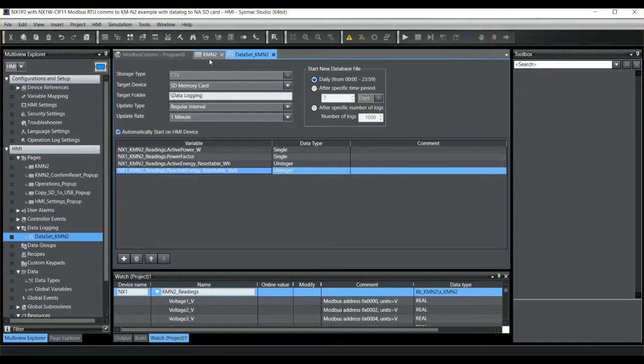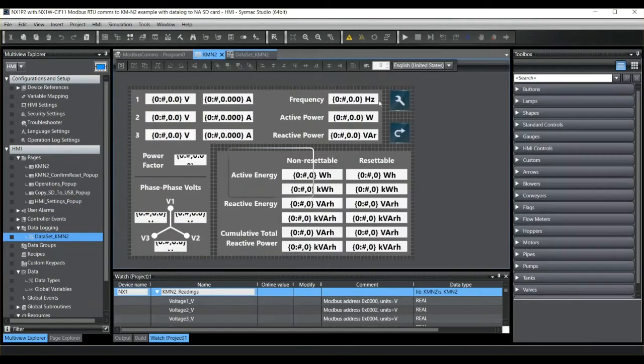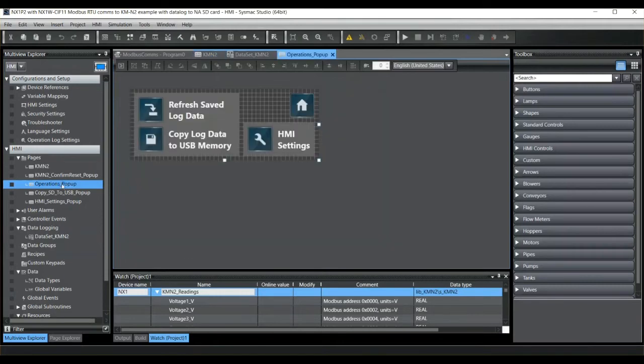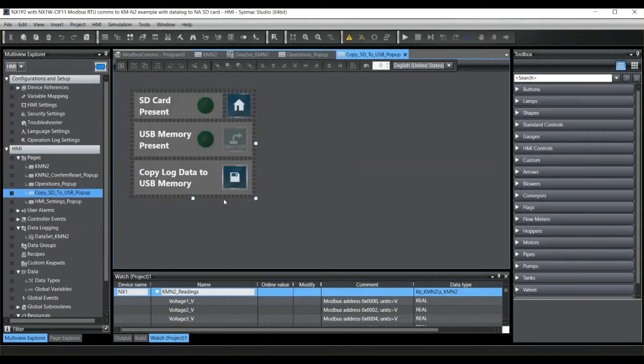Back on the main page I have two buttons. This one opens a pop-up. In this pop-up there are two main buttons: the Refresh Save Data Log button calls a function that exports any log data sitting in a buffer to the relevant CSV file on the SD card, thus ensuring the most up-to-date data is saved. The Copy Log Data to USB Memory button opens another pop-up, which shows whether we have a memory stick plugged in or not, and then lets the user copy the log data from the SD card to the USB memory stick.